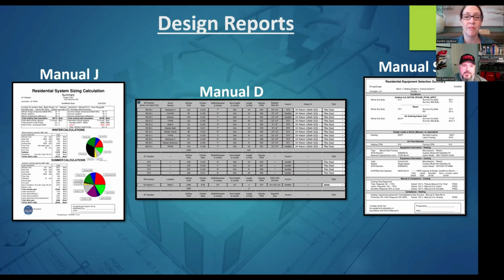How are you sizing this duct to feed air to this particular bedroom? And if he just says, well, a 7 inch is going to blow 100 CFM, well, red flag, no it doesn't. There's a calculation that goes into it. You have to do the engineering on it.